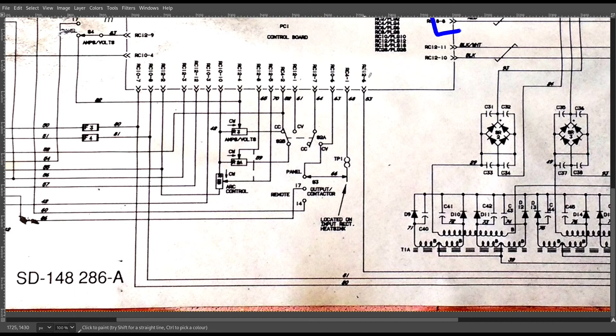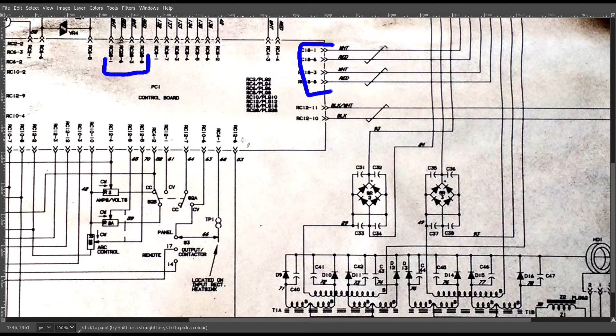This one is the one that's actually used for the main control loop, if you will. So this one will follow your main dial if it's set on CC mode, or if you're in CV mode, it still needs this signal.